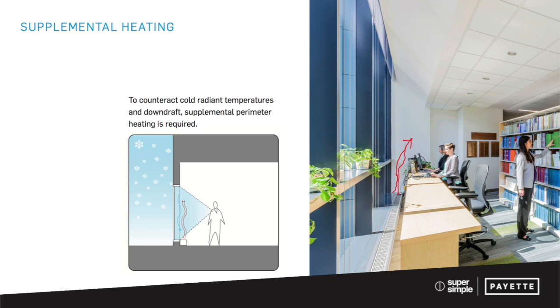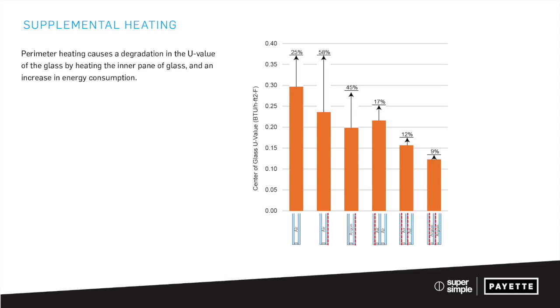In traditional design for buildings in the northern part of the country, we put in a perimeter heating system — often radiant heating — as a supplemental system in addition to the main mechanical system like a VAV. That perimeter heating is really just to keep the glass warm enough so the space stays comfortable. However, it uses more energy because we're running a separate system, and it actually degrades the performance of the glass by raising its effective U-value — heating up the glass minimizes the air film resistance. It's the least efficient spot to locate heating because so much heat is thrown right out the window.